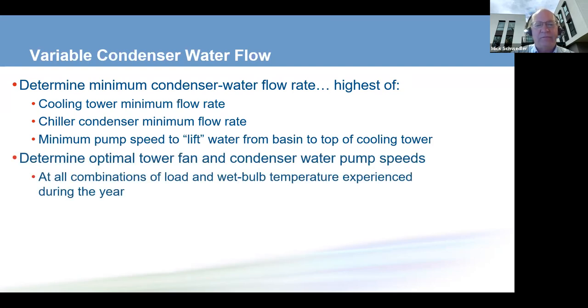Once we do that, now we have to figure out how we are going to control the condenser water pump speed, the cooling tower fan speed, and the chiller in order to optimize the sum of the chiller plus condenser water pump plus cooling tower fan kW. And frankly, it's hard because you have to do it at every different load condition, at every different wet bulb temperature condition. All the controls providers have ways to do it for you today, but they're pretty much all black boxes. So you have to trust the controls provider to do it, which is a choice.